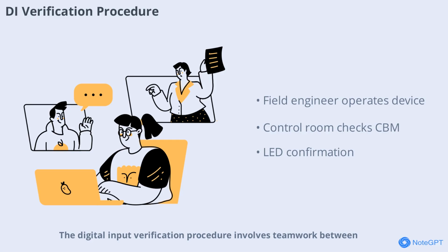Digital input verification procedure involves teamwork between the field engineer and the control room engineer. The field engineer physically operates the device, such as toggling a limit switch, while the control room engineer observes the corresponding variable in Compact Control Builder (CBM) for state changes. Additionally, the module's LED should light up, confirming the signal's journey from device to software. This hands-on process ensures that every input is accurately mapped and responsive, laying the groundwork for reliable system operation.